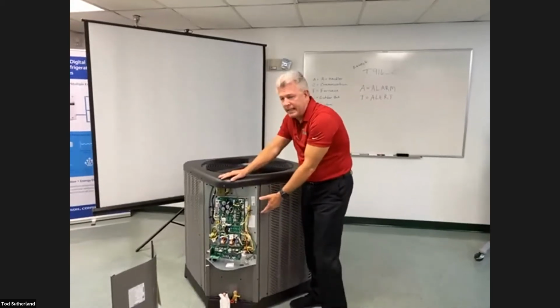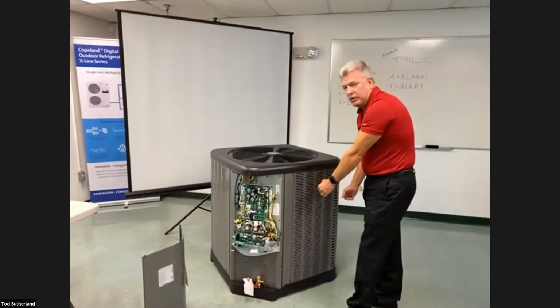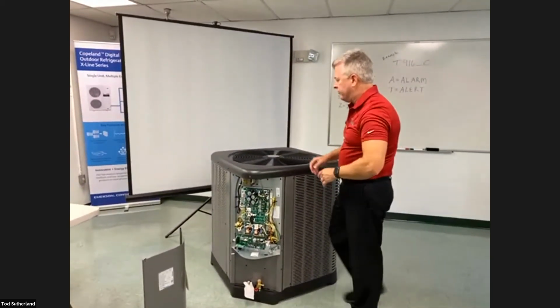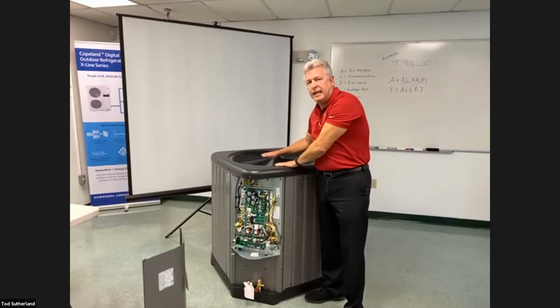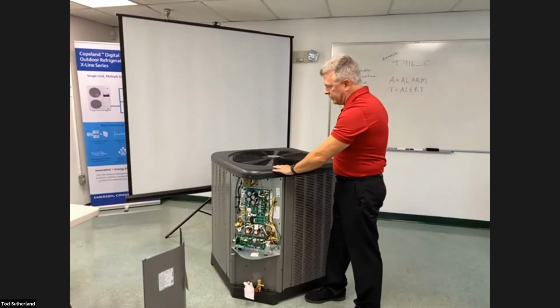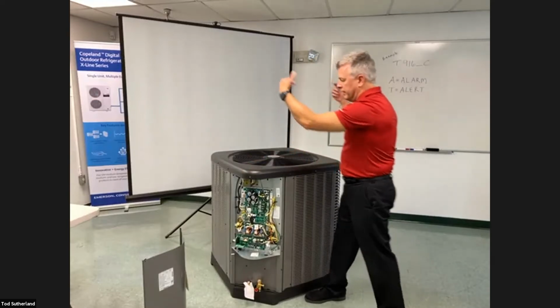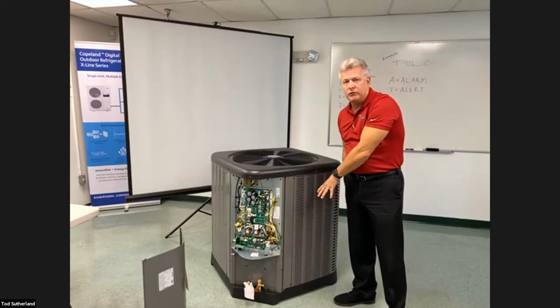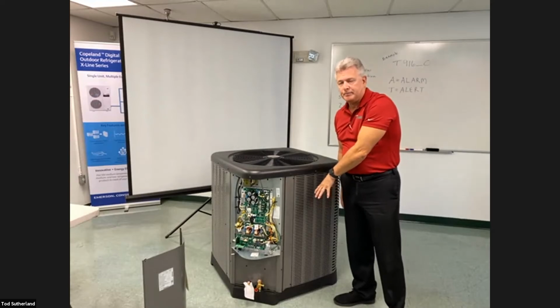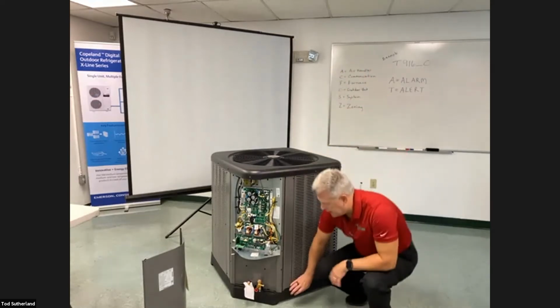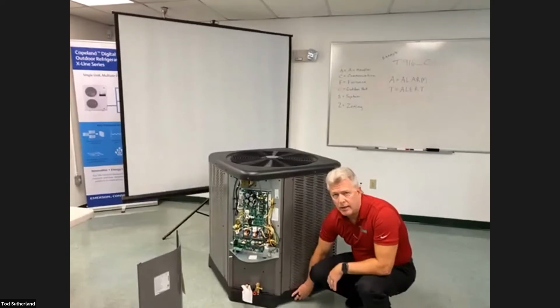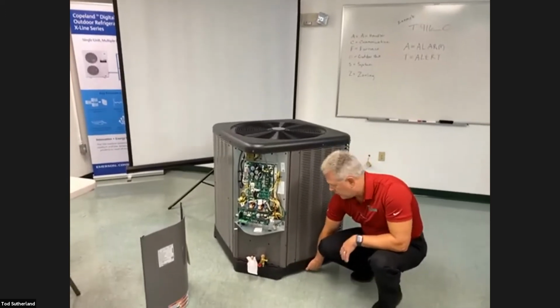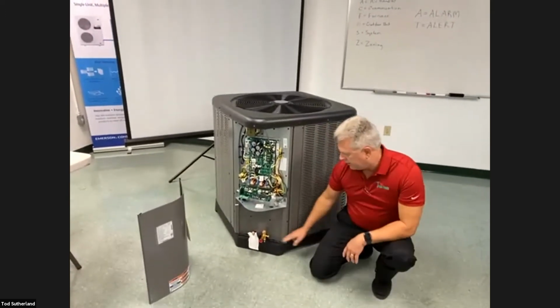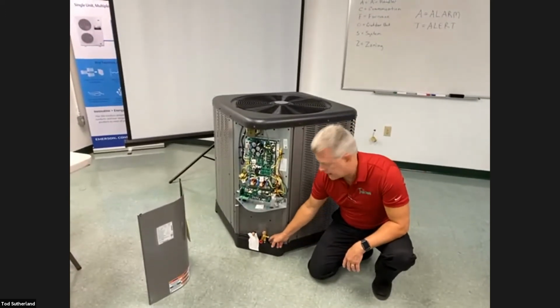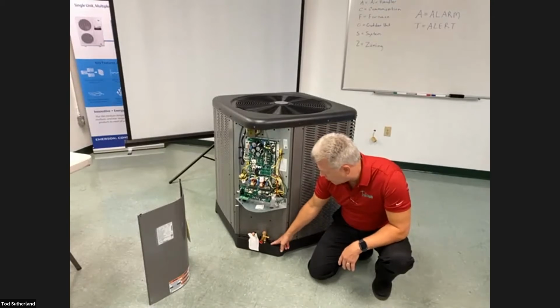There's enough wiring in there that you can slide this whole panel over here to the right. There's also enough wiring on the condenser fan lid that when you remove the screws around the lid, you can remove the lid, flip it over and lay it down beside the side of the condensing unit. All the Ruud units have this base pan on it now, this polymer base pan, where you have a finger grip here. You've got slots for your screws. They have drain weep holes in them for your water.